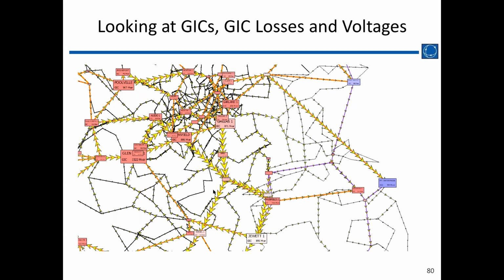There's a question in the chat about whether there's anything to simulate protection tools such as neutral blocking devices. I can answer that by simply saying yes. As far as neutral blocking devices go, protection tools, I guess it could be broader than that, like relays and things like that. A lot of that relay protection can be put into the transient stability analysis, but a lot of it is not, particularly things that might operate over longer periods of time that could be important in a HEMP event.